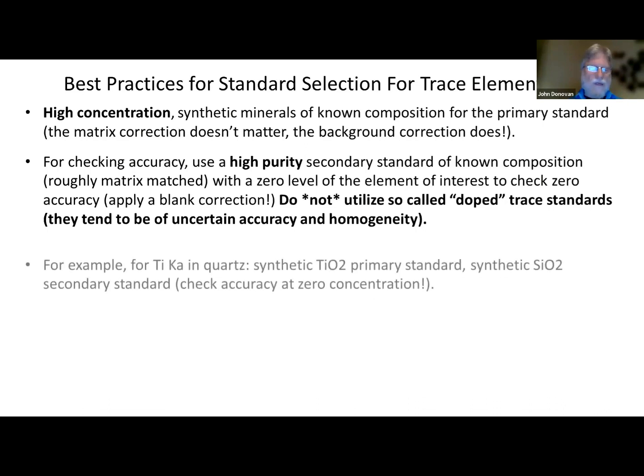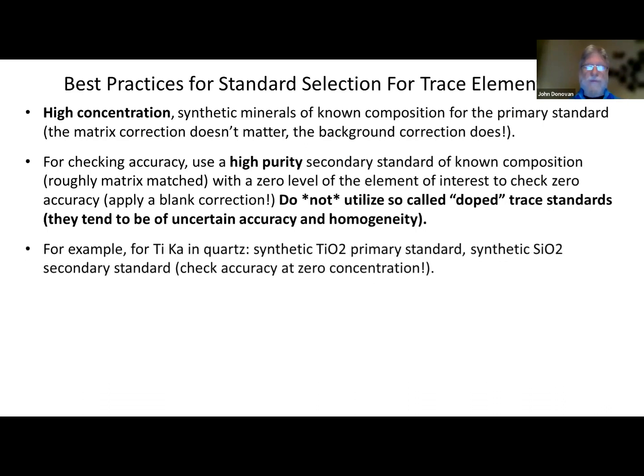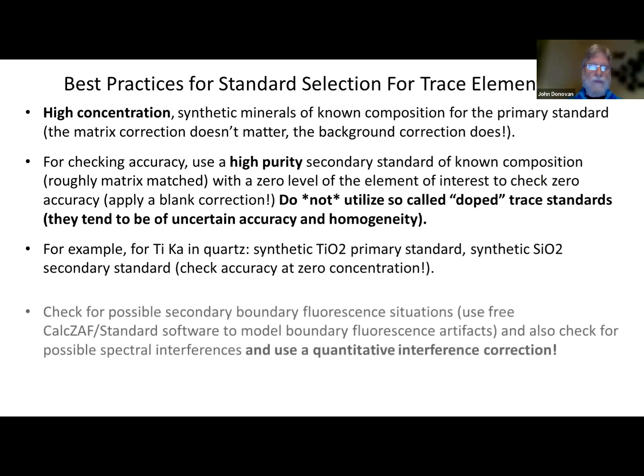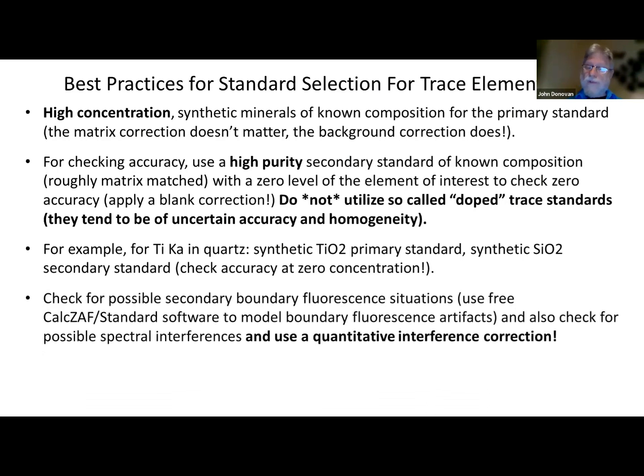All right. So for example, for measuring titanium in quartz, we use a synthetic TiO2, and we check the accuracy using a synthetic SiO2. And then also check for secondary boundary fluorescence corrections.